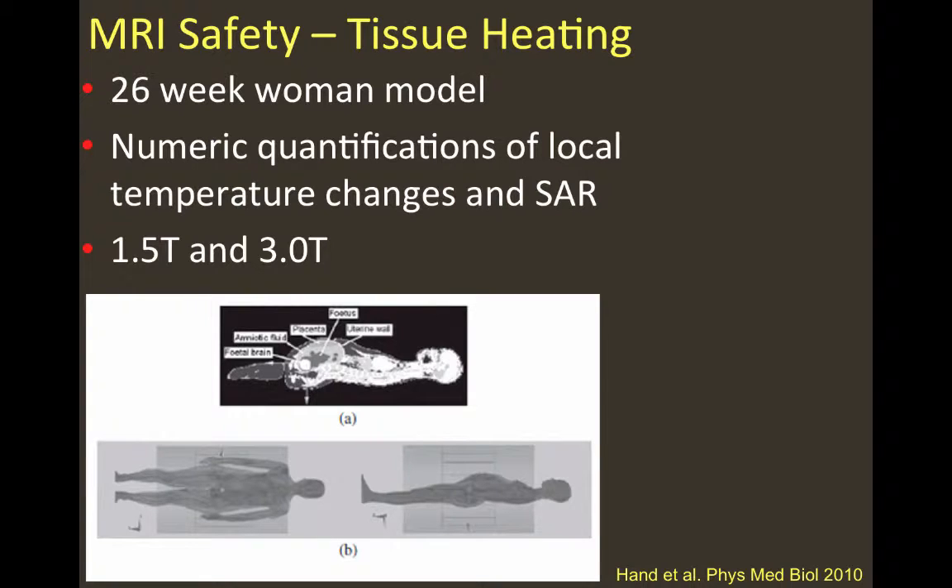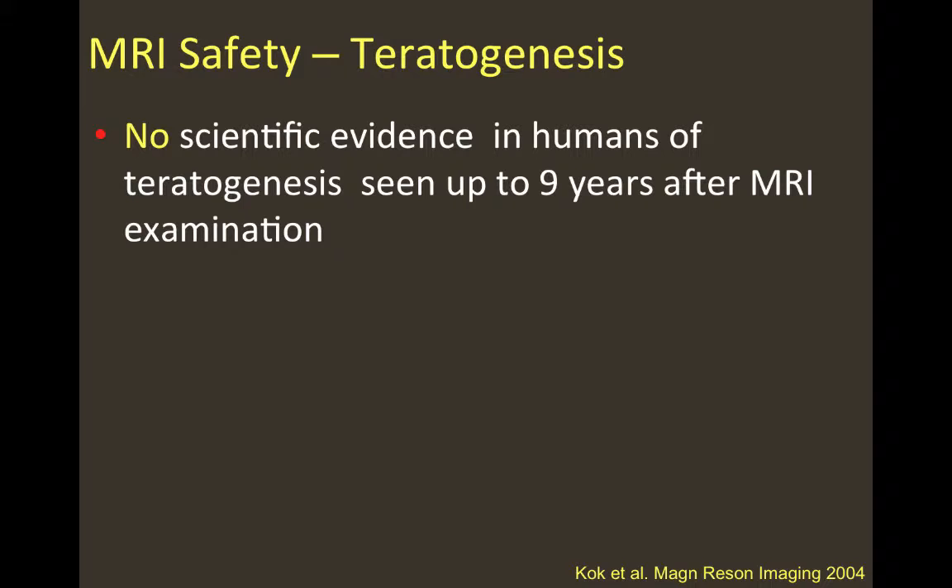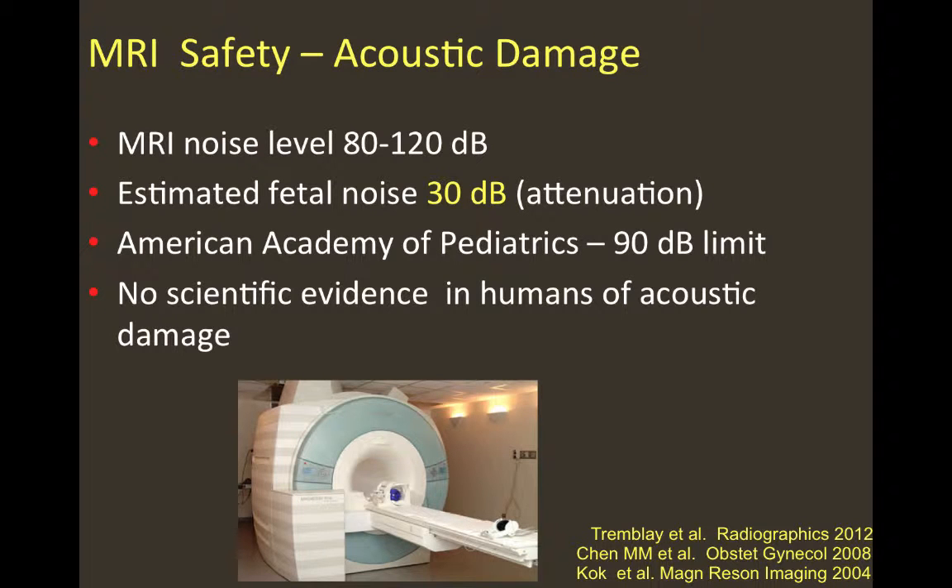Hand and colleagues conducted an experiment using a phantom simulating a 26-week pregnant woman, performing numeric quantification of local temperature changes in SAR at 1.5 Tesla and 3 Tesla magnets. They found that fetal effects are within international safety limits for SAR less than 2. No scientific evidence of teratogenesis in humans was recorded in experiments conducted up to 9 years after MRI examination. Regarding acoustic damage, MRI noise levels can approach 80 to 120 decibels, but estimated fetal noise due to attenuation by the mother's body is no more than 30 decibels — well below the American Academy of Pediatrics' proposed 90-decibel limit.